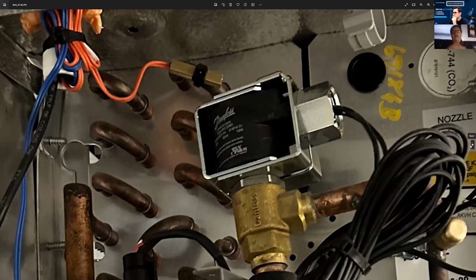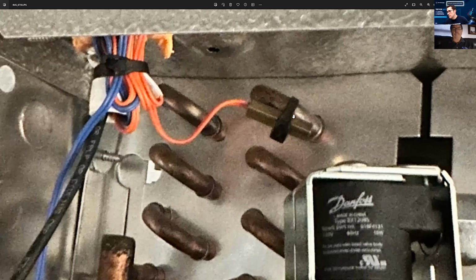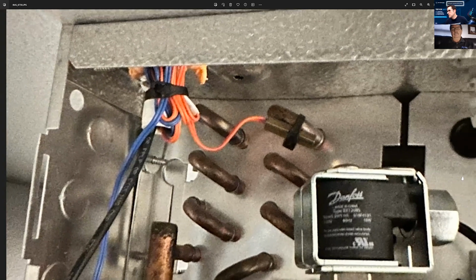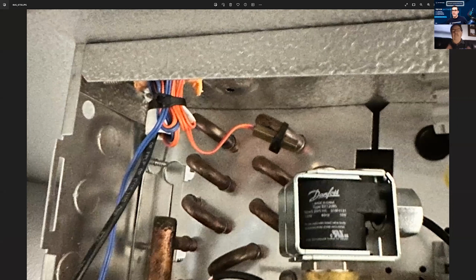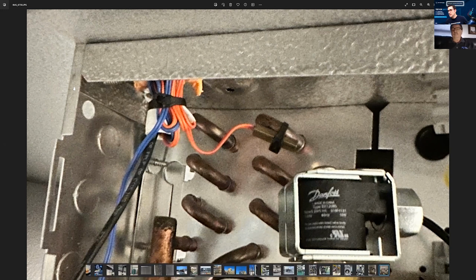And on Heatcraft, or any evaporator, go by the manufacturer specifications. On that one, it used to be the third return elbow down on the front. They have since changed that because we were getting a little bit of frost buildup on the bottom of the evaporator. They wanted to go midway down on the front of the evaporator. So this is in the manufacturer's information. This is a little bit better, but you want to go straight across with them. You want to get as much contact as possible, and that gum insulation around there is really good. For sure, it's perfect.